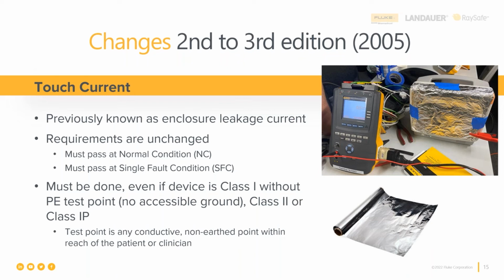So inside the medical device, all wrapped in plastic with no other conductive test points to use, we have conductors and current flowing. Then we have this plastic chassis that is an insulator. Whenever the patient or the clinician touches that medical device and touches the patient, there will be a current flow. And we must know how much, where it is flowing, and under several different conditions. We have to know that.